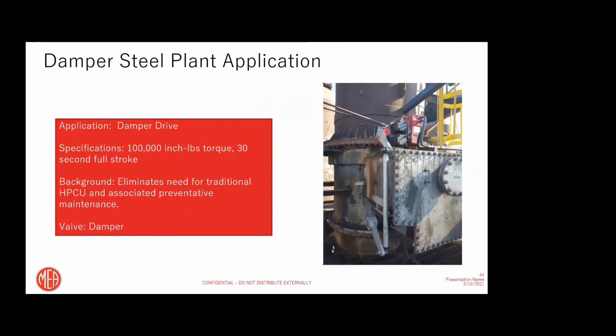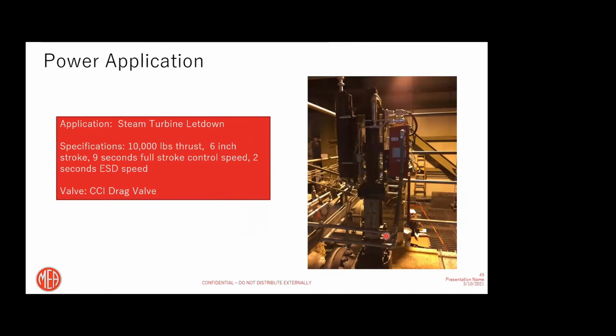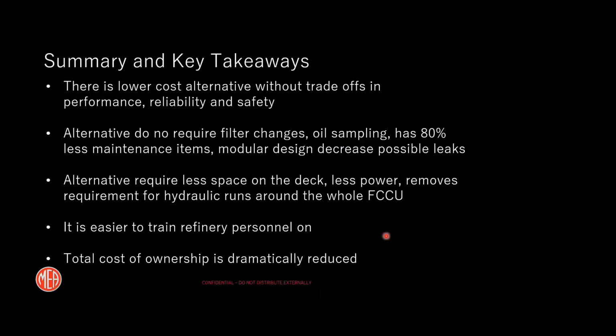So whenever you need a lot of torque or a lot of thrust and very precise control to operate your actual burning process, you can utilize these units there too. Steam let-down, steam turbine let-down valves, same thing. Basically, you can apply these units there. So just to outline key takeaways, there is a lower cost alternative without trade-offs in performance, reliability, and safety if you compare a Hawk to HPCU.